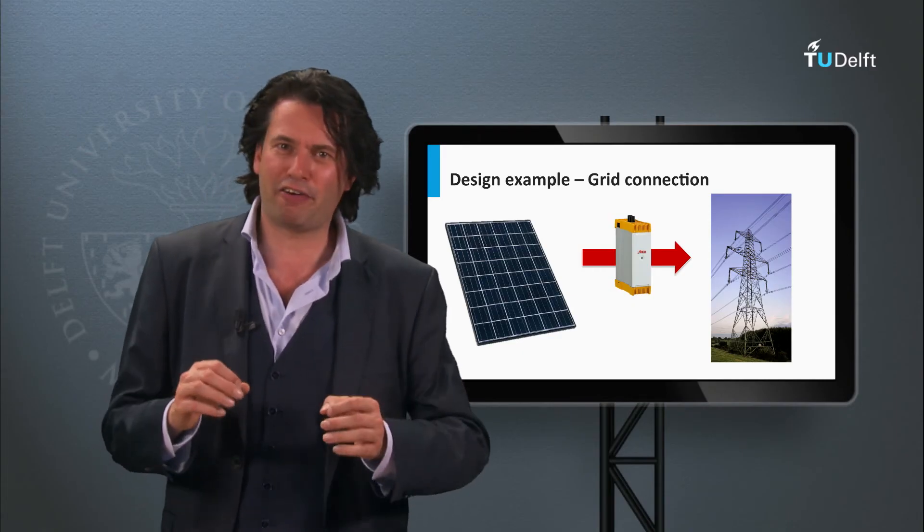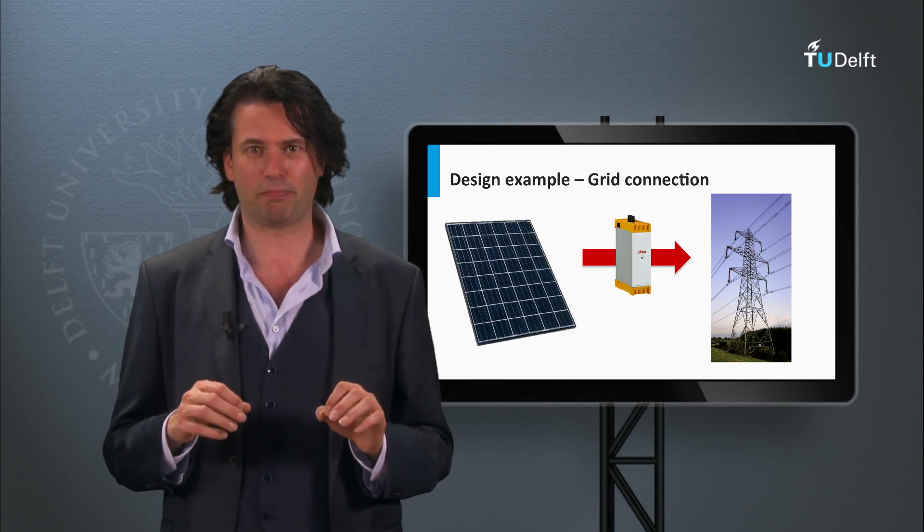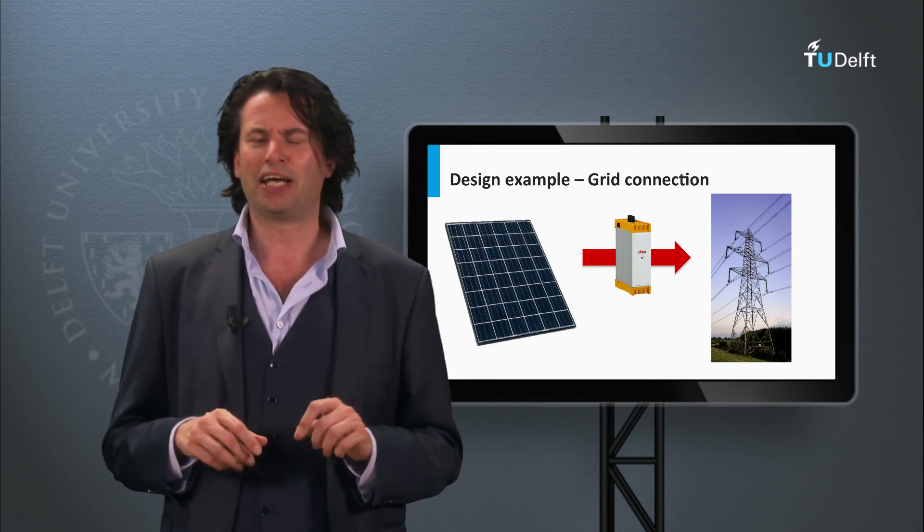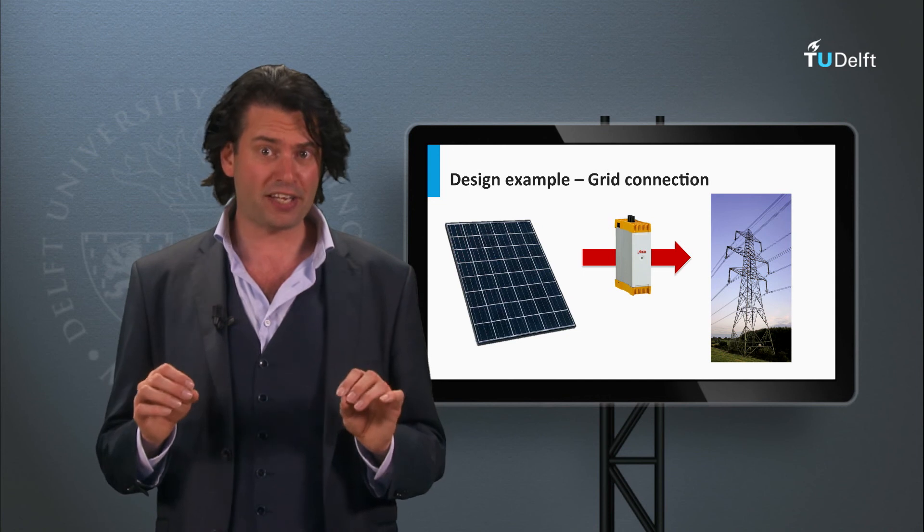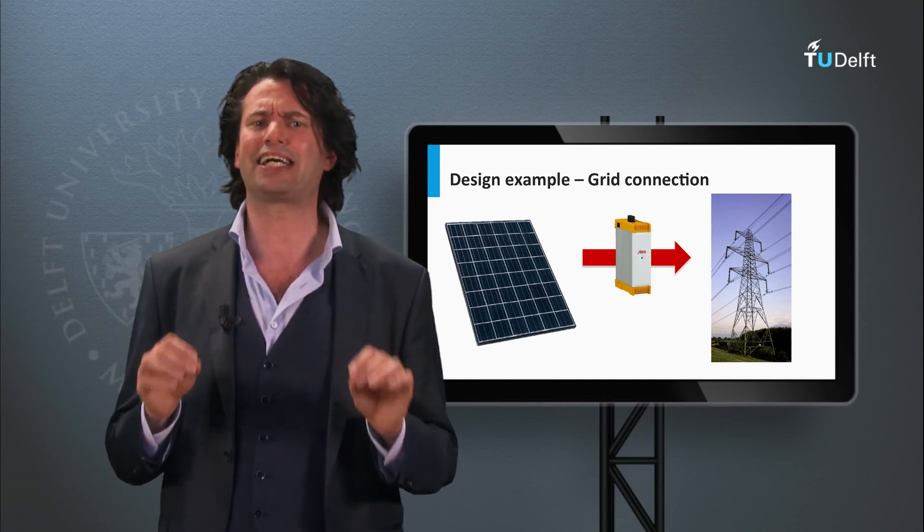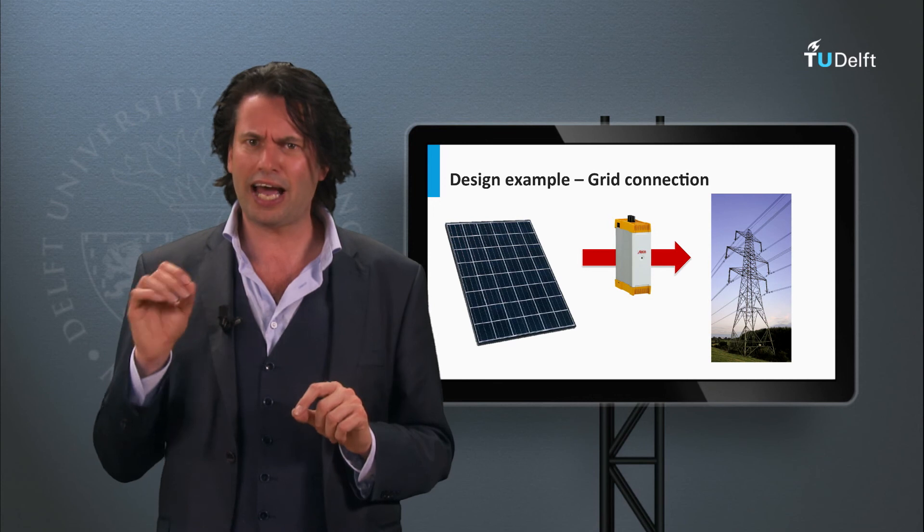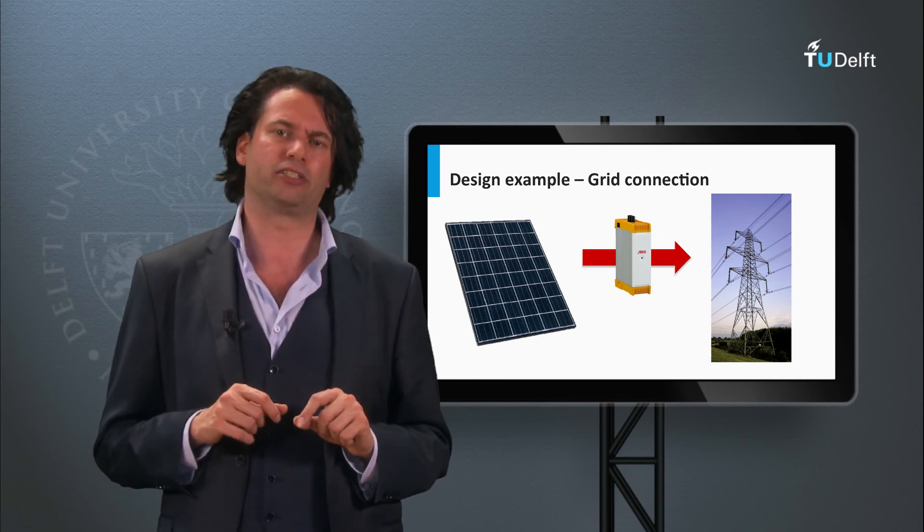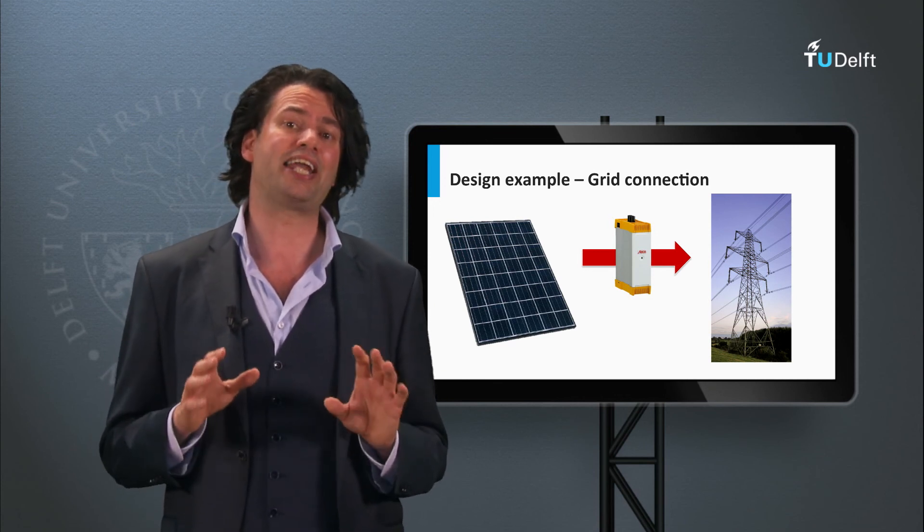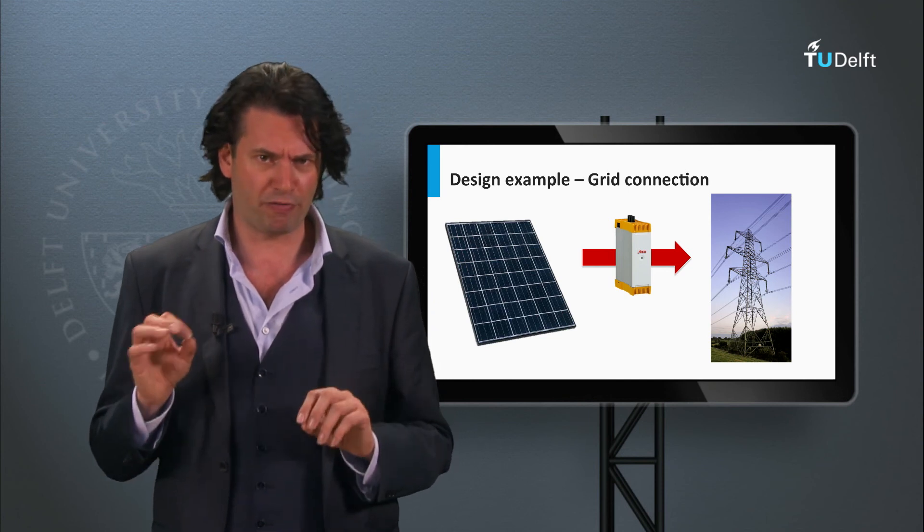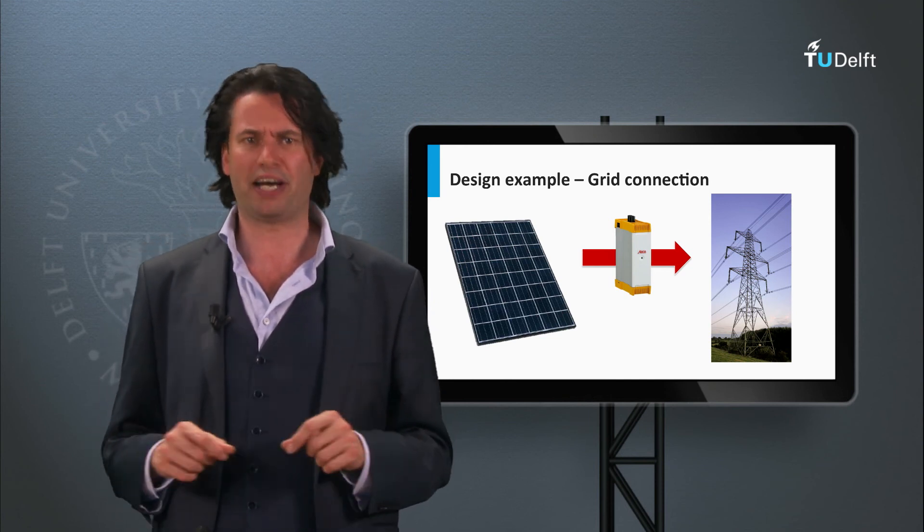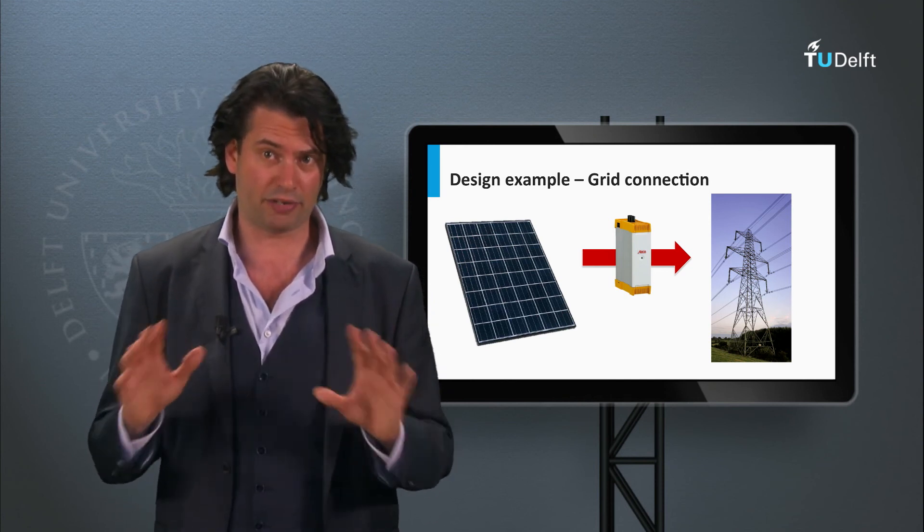Now I must clarify one thing about the grid-connected PV system. Usually, the amount of PV panels or the rating of PV panels need not be exactly as per the load requirements, like it was in the stand-alone PV system. This is because any excess or deficit of PV power can be compensated by the grid.